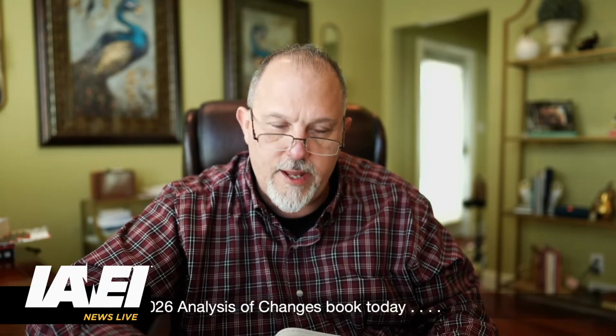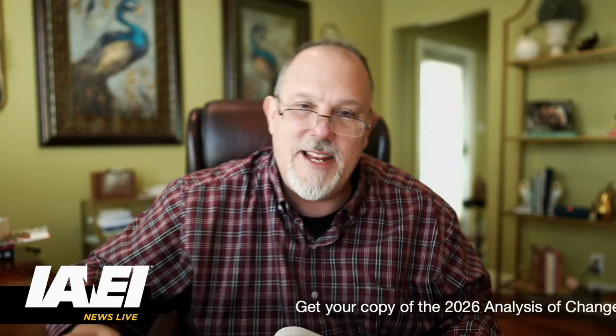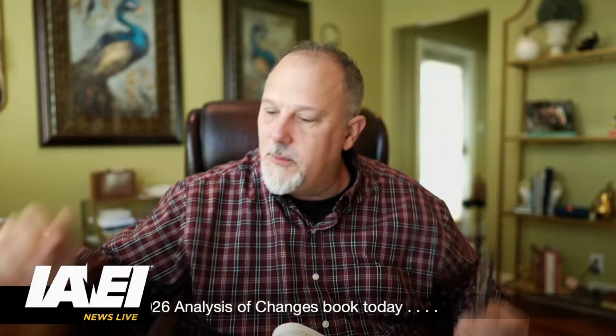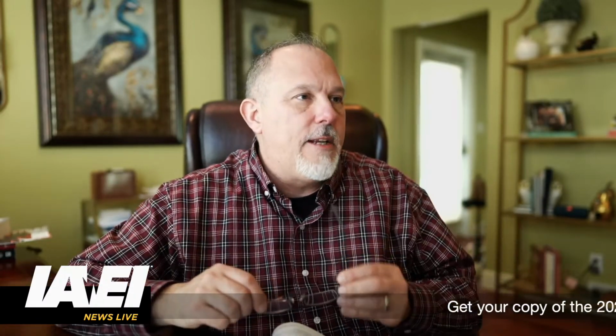13 and 14, we have indoor damp locations, and in 14 we have indoor wet locations. We got rid of the whole debate of is it 'or' or is it 'and', so we just eliminated the word altogether. That solves the problem. Usually when people put in a public input saying they don't like this word or that word, we just get rid of it. In this case, we didn't expand anything. That was all we did in A.